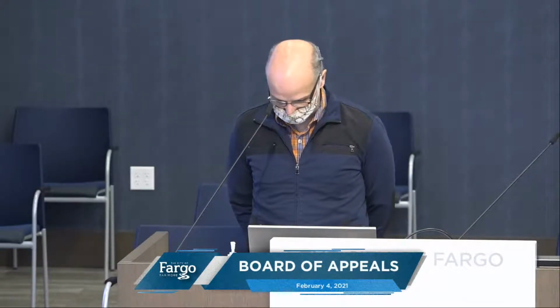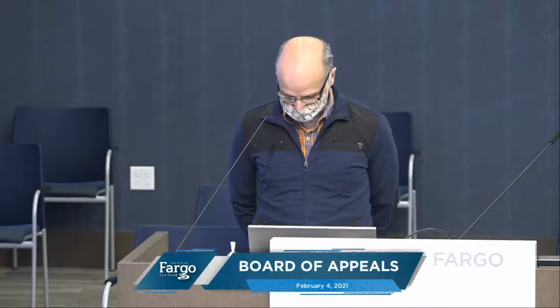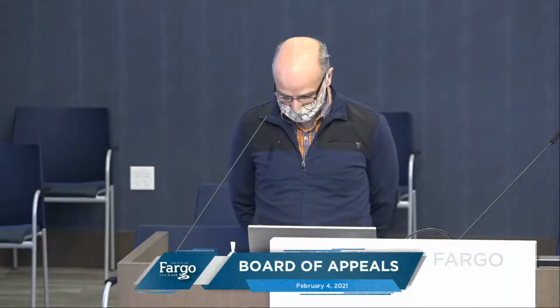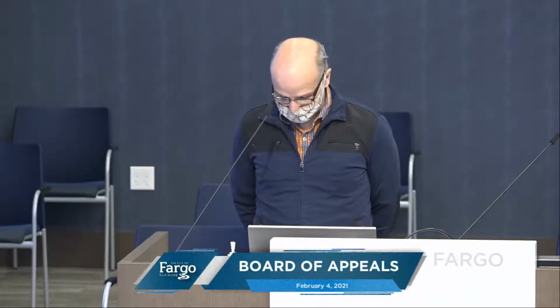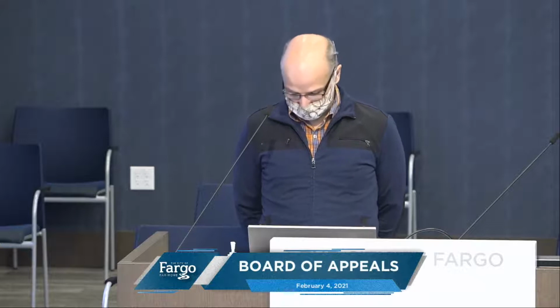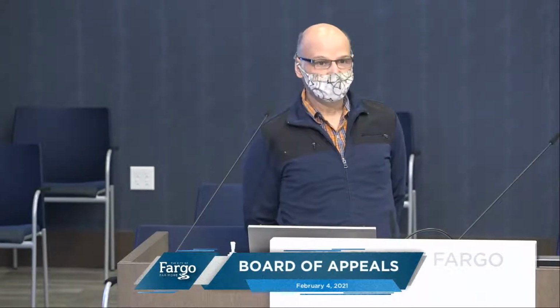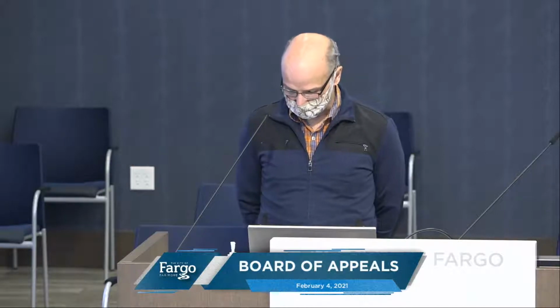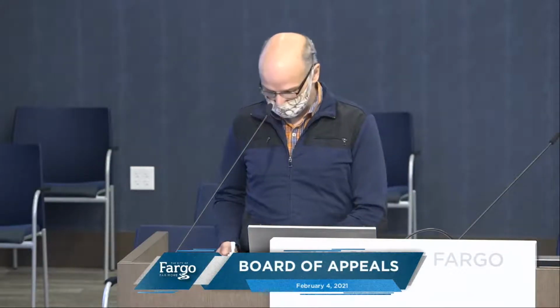I do want to comment on a couple of things, rebut a couple of things. Bruce has brought up footnote B of Table 508.4. The section that I asked him to repeat, he did say, the required separation from areas used only for private or pleasure vehicles shall be reduced by 1 hour, but not to less than 1 hour. The subject of that sentence is the required separation. When there is no required separation, it cannot be reduced.